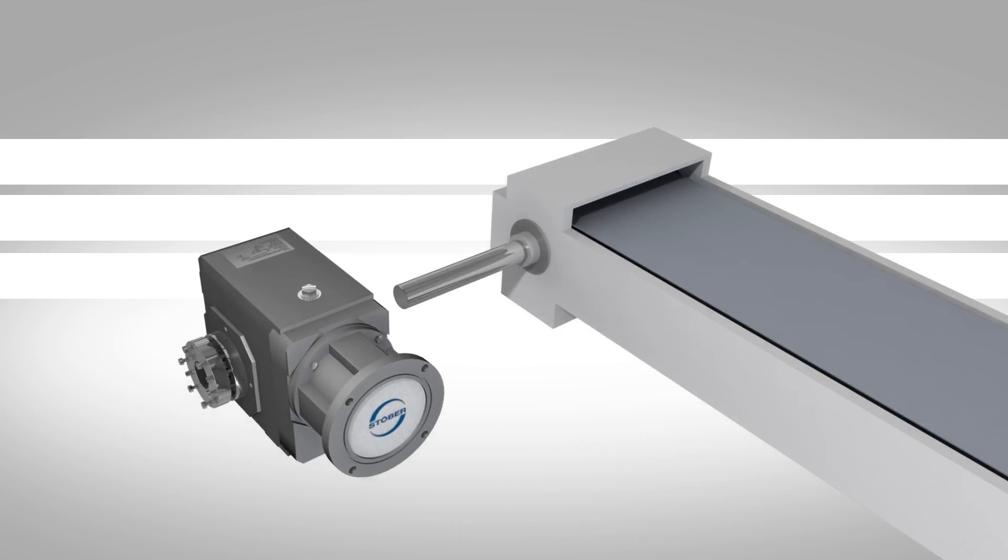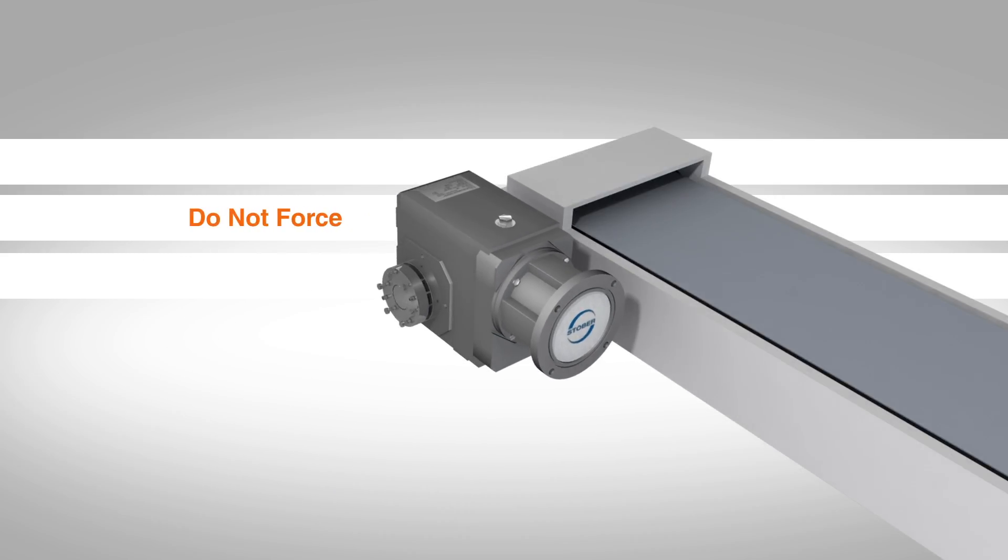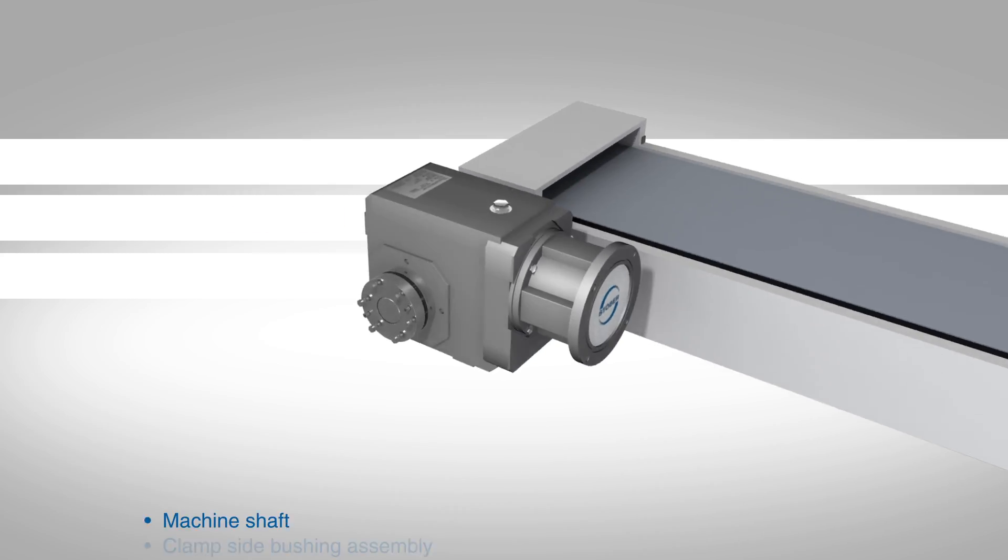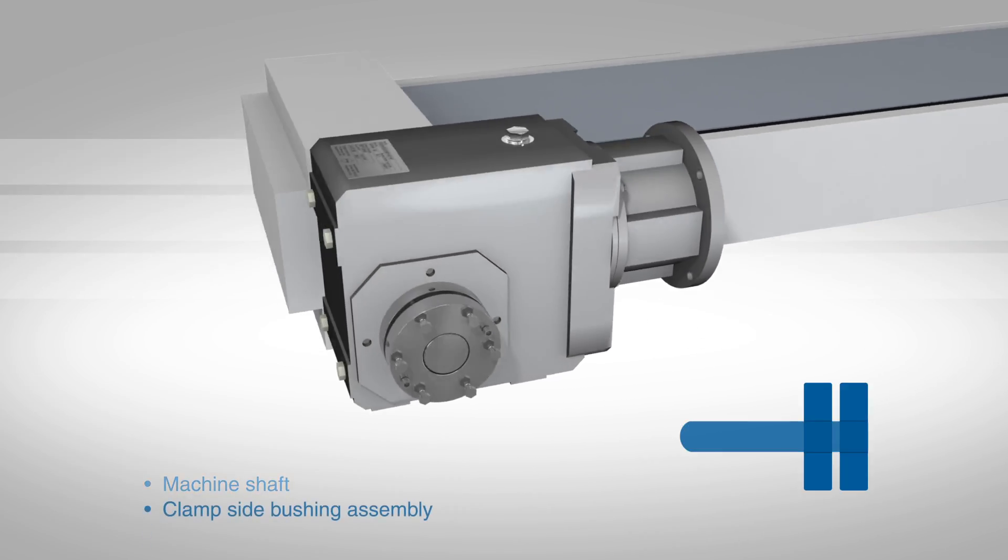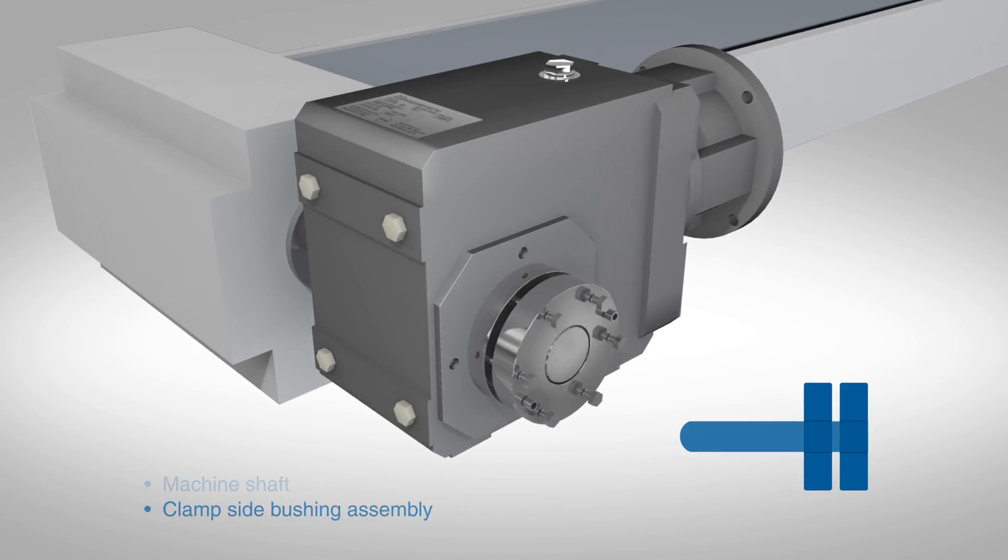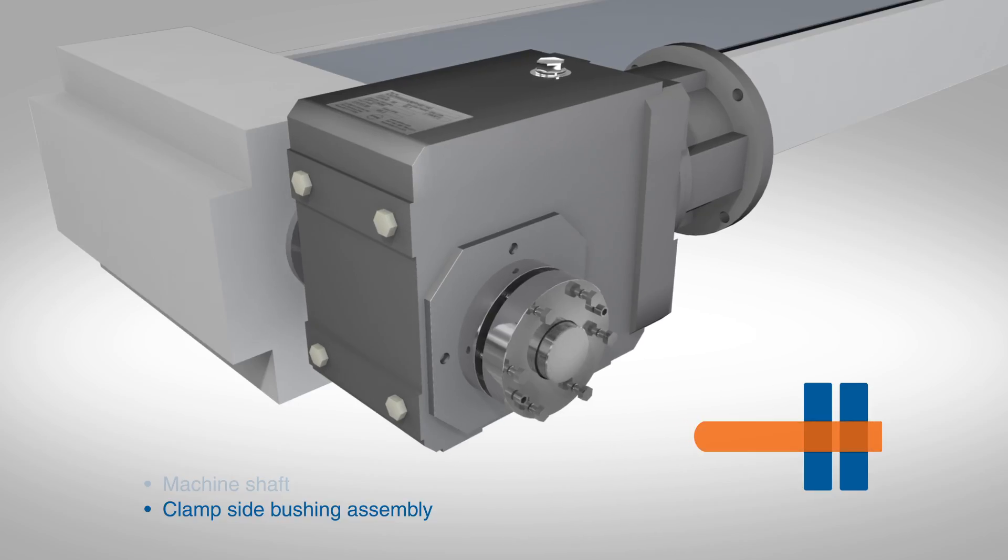Guide the reducer, support side first, onto the shaft. Do not force the reducer onto the shaft. When correctly positioned, the end of the shaft should be flush with the clamp side bushing ring. Too much shaft extending through the bushing will not allow the covers to be installed.